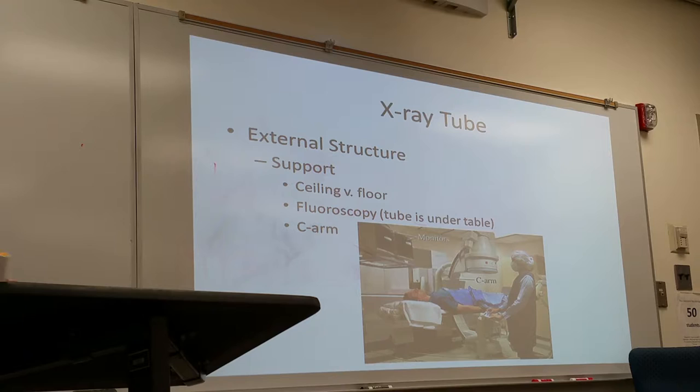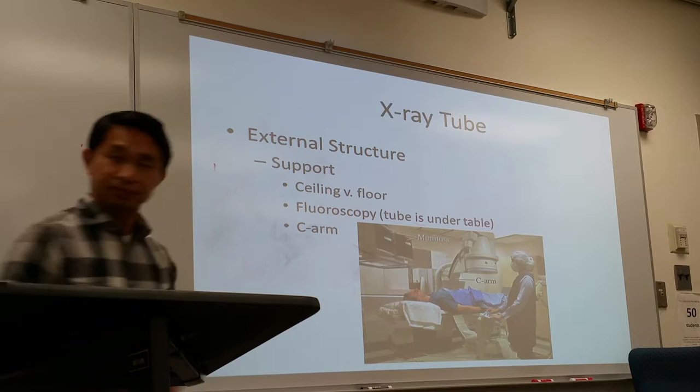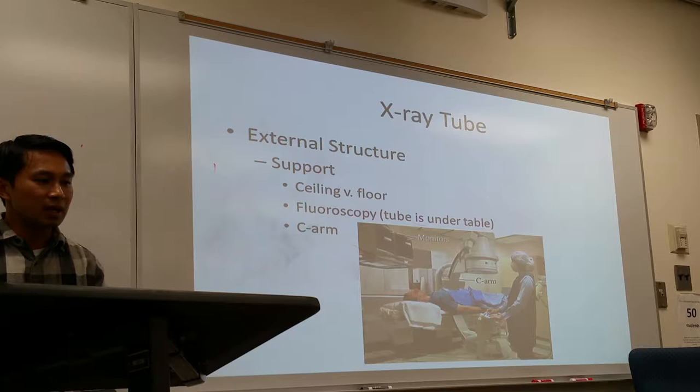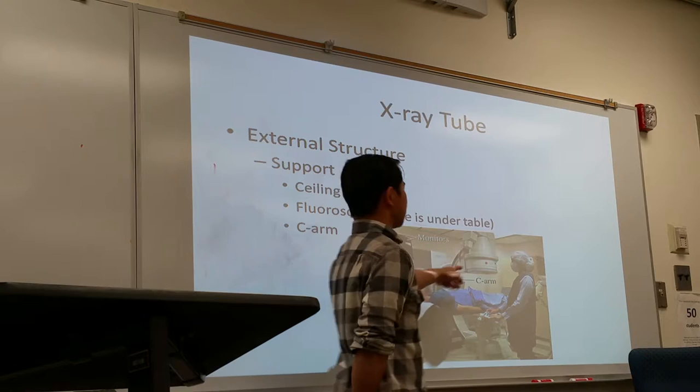Floor support is very limited in terms of where you can manipulate the x-ray tube. Sometimes you can only go back and forth with the floor support system — there's a rail underground, just some sort of attachment, and you just move the tube back and forth. Other floor tubes are built underneath the x-ray table, so when you use a floor procedure.